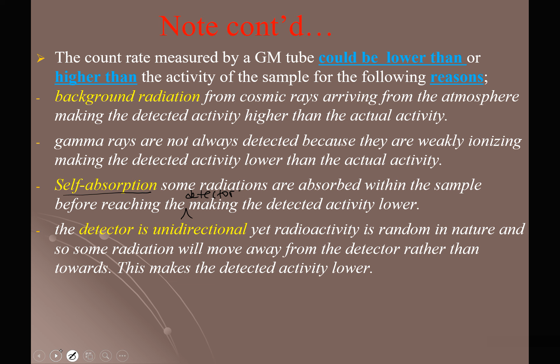Number 4, the detector is normally unidirectional. Remember, radioactivity is random, which means the particles emitted can be emitted in any direction. But because the detector is unidirectional, it only detects radiations which are coming towards it. If an alpha particle is emitted in a different direction from the detector, it is not going to be detected. So some radiation will move away from the detector rather than towards it. Of course, if those radiations are not detected, the registered activity is going to be lower.